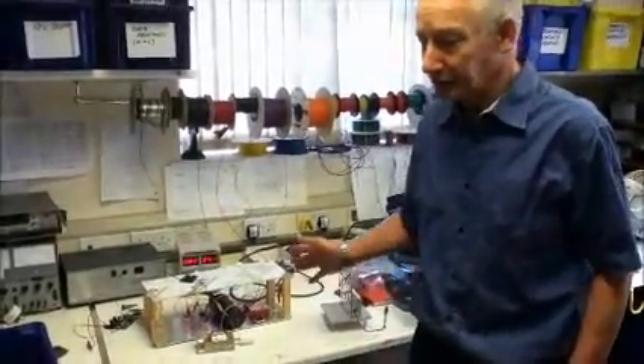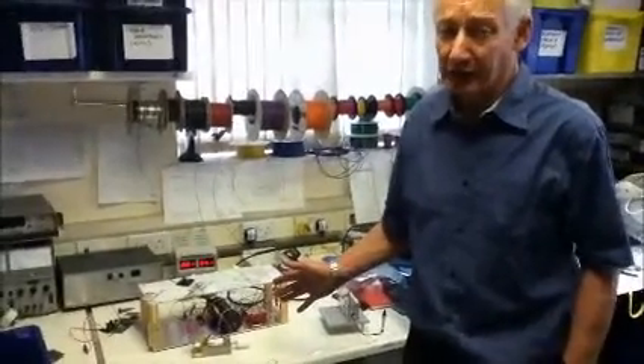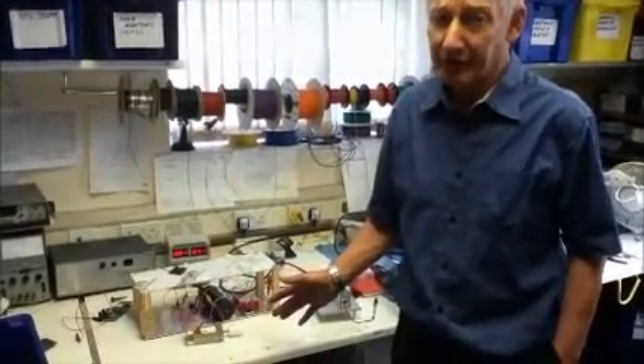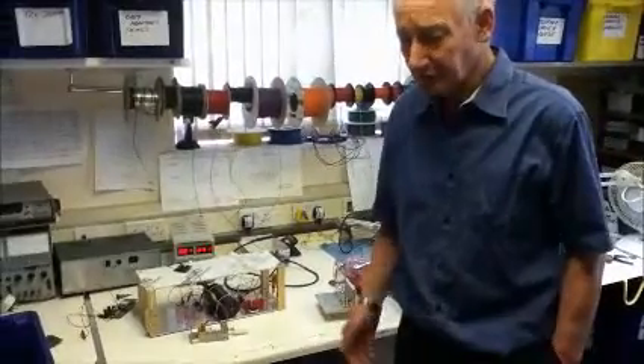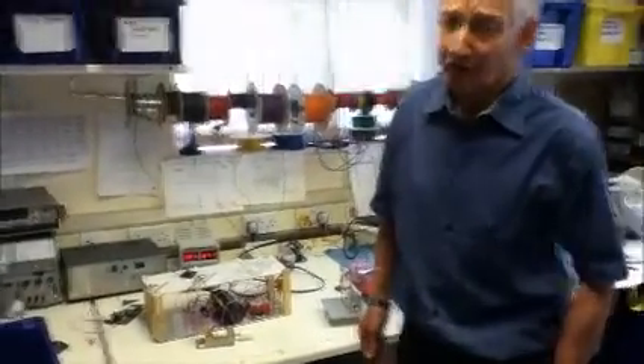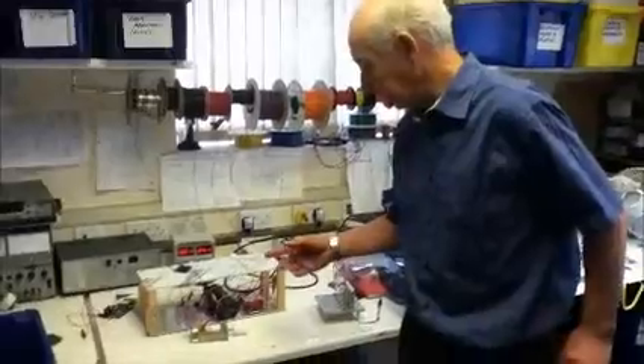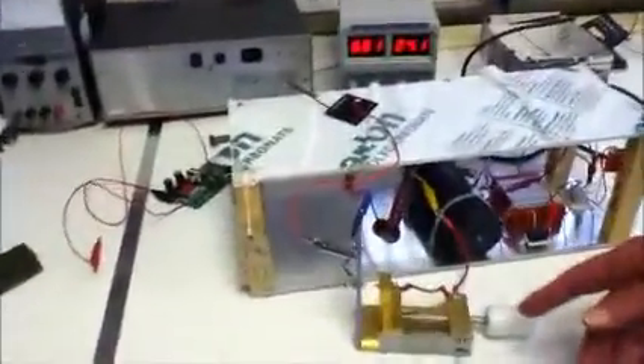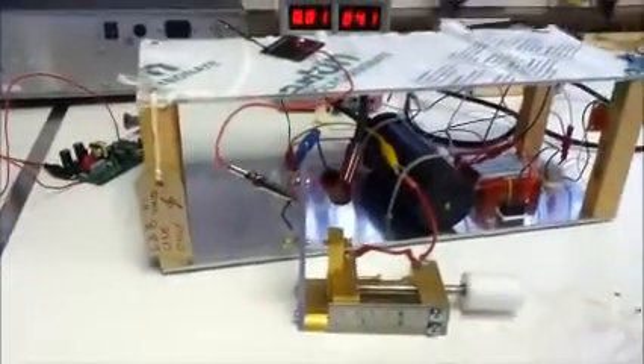So the approach we took was to put a spark gap with a calibrated distance in parallel with the test piece, so we can give it a surge, which is quite testing, and at the same time have a very good idea of what the voltage has gone to. So we've got a couple of setups here, and you can see the development spark gap we've got here, which is a piece of brass.